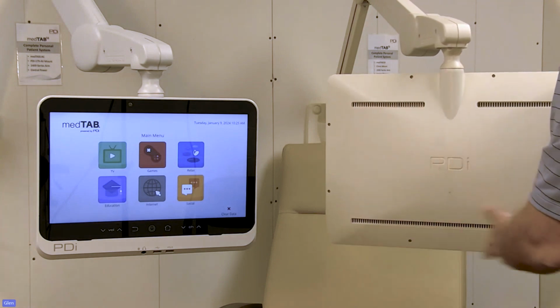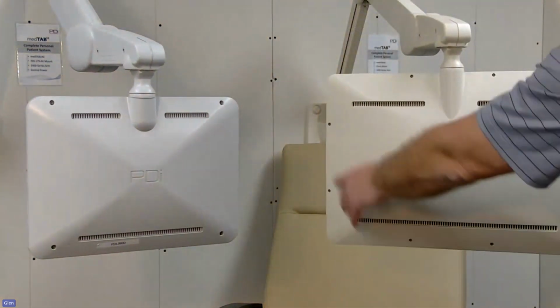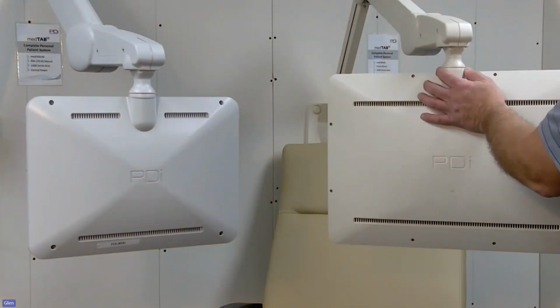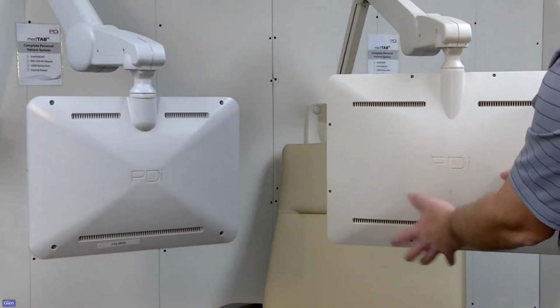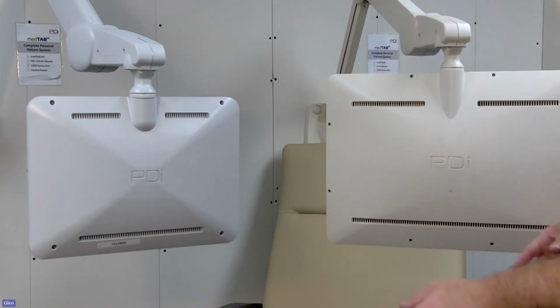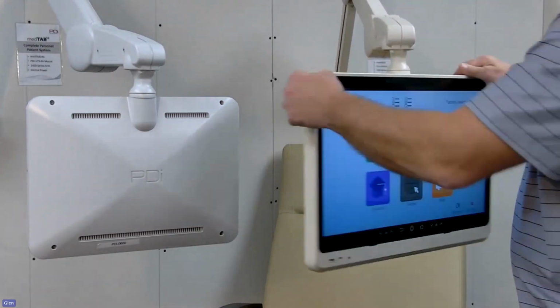We do have a few more screws because of the size than the 16-inch does. It only has 4 mounting screws. This one has 8. Again, larger footprint. But when these are unfastened, this device will drop from the collar and can be hinged up and out of the way. If you wish to do maintenance on the device, on the arm, it could be done.